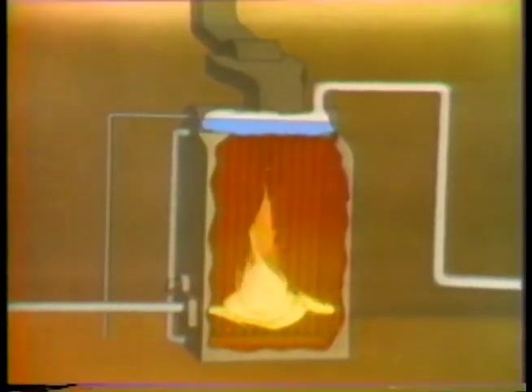Additional heating by radiation results from the boiler flame. This radiation only affects the part of the water walls which are in direct line of sight of the flame. Heat transfer by convection occurs as the hot gas rises in the boiler furnace. While natural circulation of the flue gas will occur, modern boilers have fans which create a forced circulation and improve the efficiency of the convection.